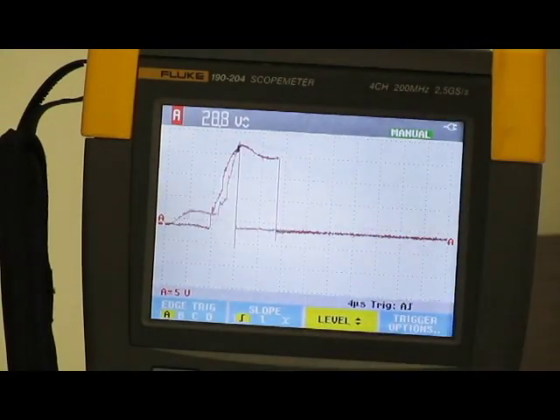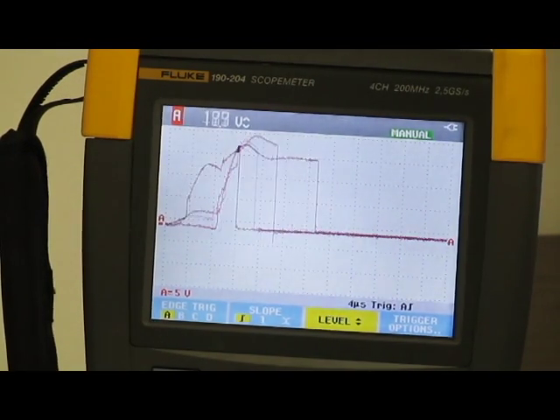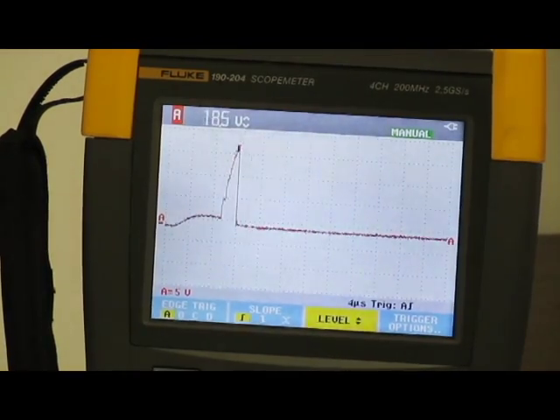These very sharp discharges are the discharges that are actually going through the bearings, eroding the bearing race, which can eventually cause fluting damage in the bearing.